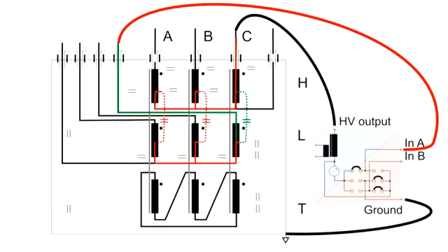If the connectors of the high voltage bushings and the low voltage bushings are not connected to each other, current also flows through a second winding. As a result, the core gets magnetized, leading to further losses, which overlay the dielectric losses. These additional losses can create conspicuous effects.